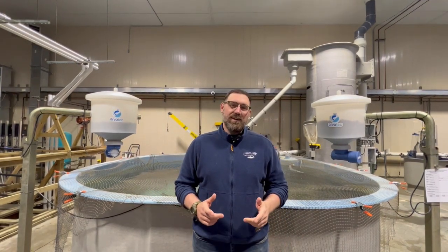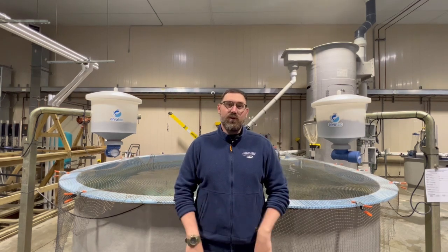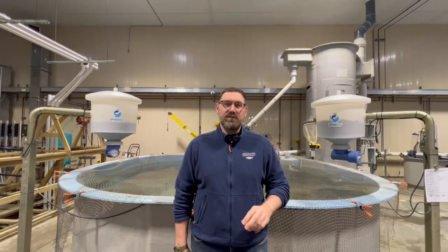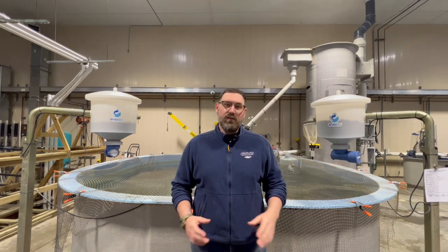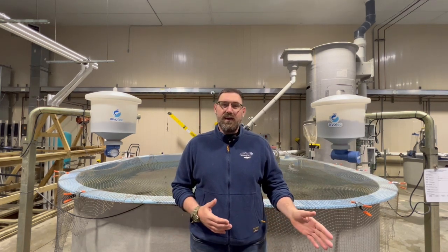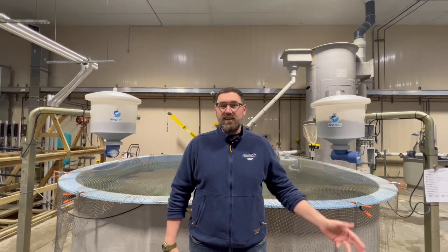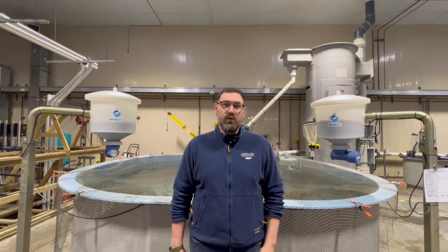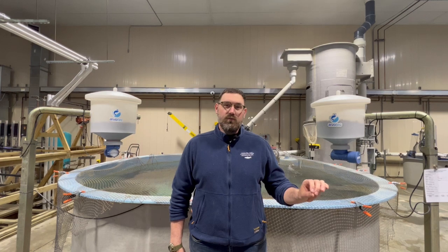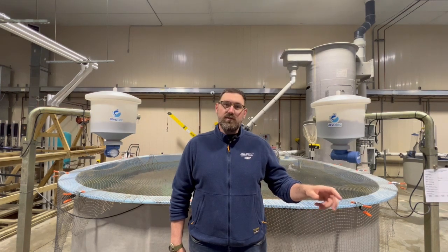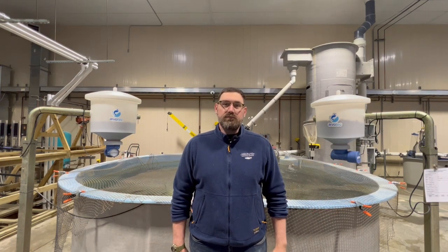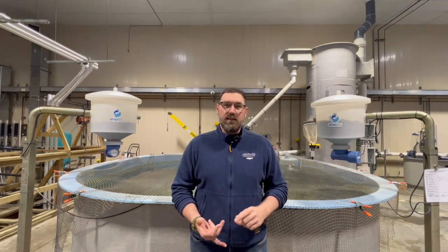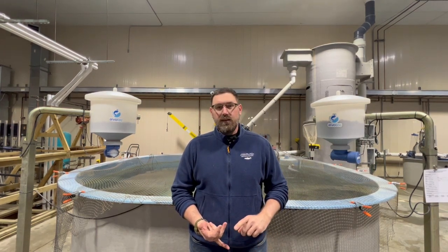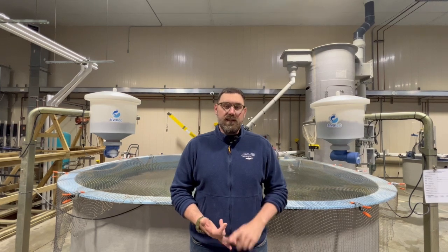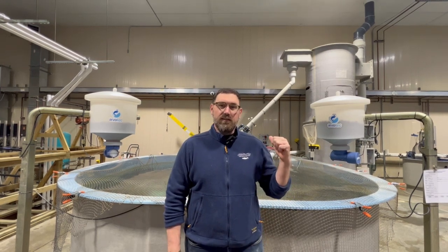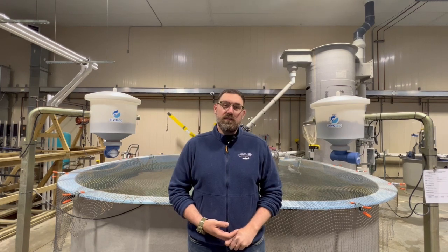I'm here today to tell you about a tool that's incredibly important for a RAS facility, and that tool is an ultrasonic flow meter. An ultrasonic flow meter allows you to go tank side and strap it onto pipes ranging in size from ½ inch to 24 inches and get a real-time flow readout so that you can fine-tune your system and optimize it. Today we're going to look at the components that make up an ultrasonic flow meter. We're going to attach one to the pipe on the system right behind us, and then do a real world scenario.